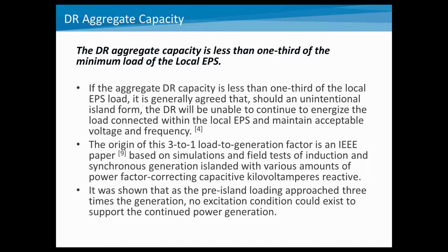So first off, you would be able to meet the requirement if the DR is less than 1/3 of the minimum load. Basically what this means is that the DR size is relatively small with respect to the local load. There are a couple of references and work that's been done showing that with this kind of ratio, sort of 3-to-1, which is pretty high, you would not be able to maintain a stable island operation for both induction and synchronous generators. It basically showed that when the pre-island condition approaches 3 times the generation, you can't really support the load. And a key thing that is often difficult to determine is what the actual loads around distributed generation are. But basically this is saying that if you have a small DR in relation to the load, you won't be able to support an island condition.